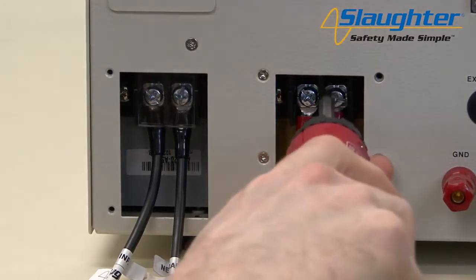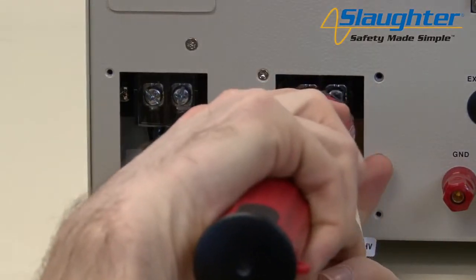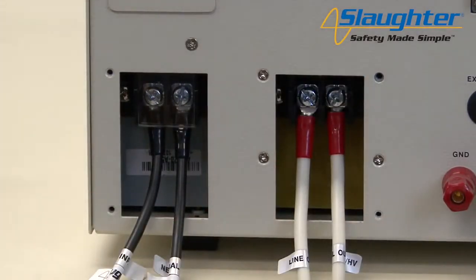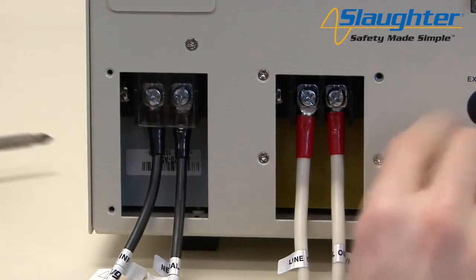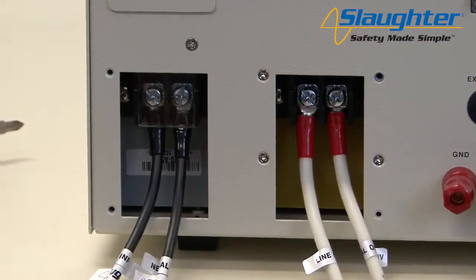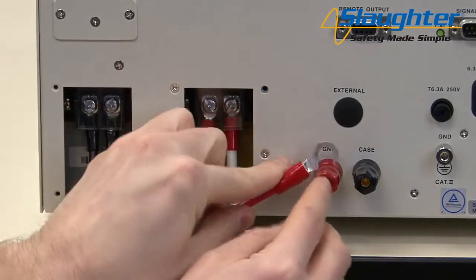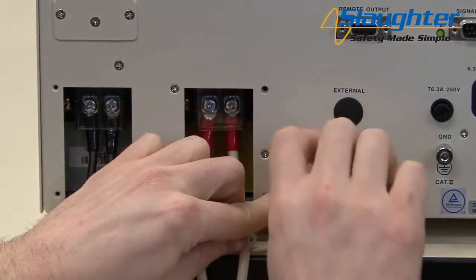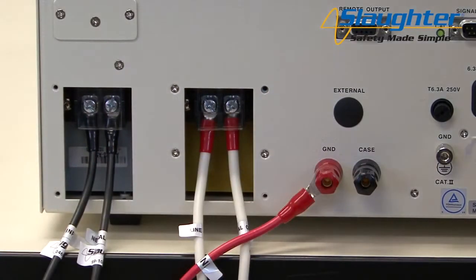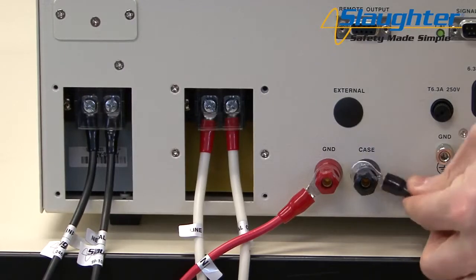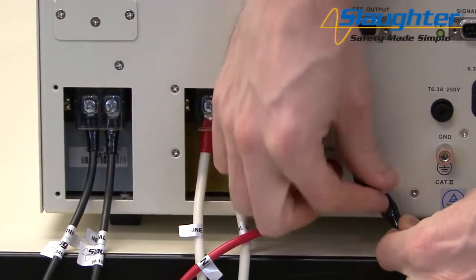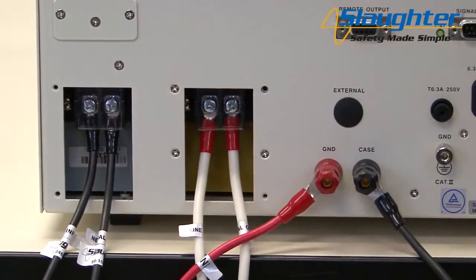Next, we're going to connect the adapter box. These connections provide power to the DUT during a run or line leakage test. Connect the adapter box to the line, neutral, and ground terminals on the rear panel of the 6330. Connect the black case lead to the case terminal. The case lead provides a return path for the Hipot, ground bond, and IR tests. It is isolated during the run and line leakage tests.